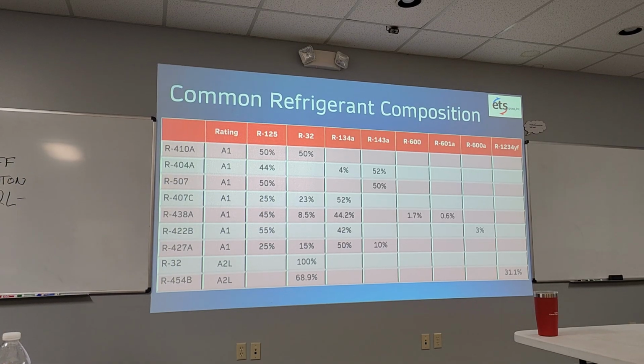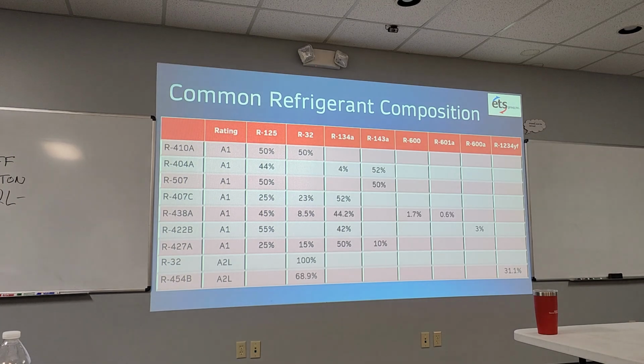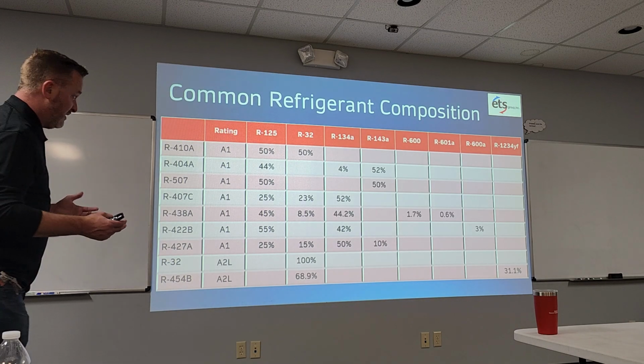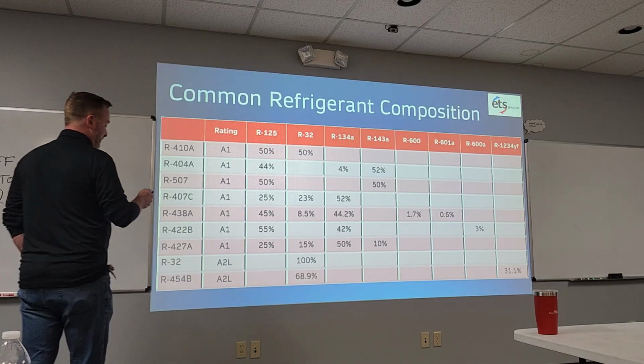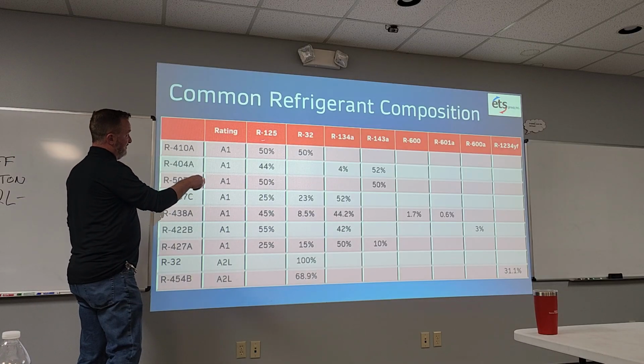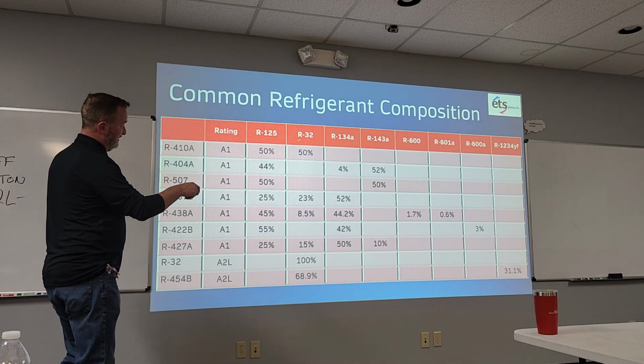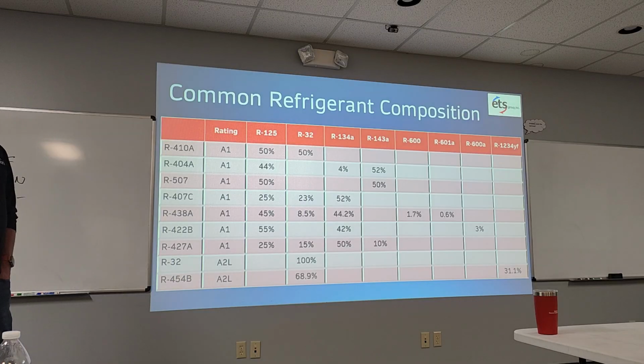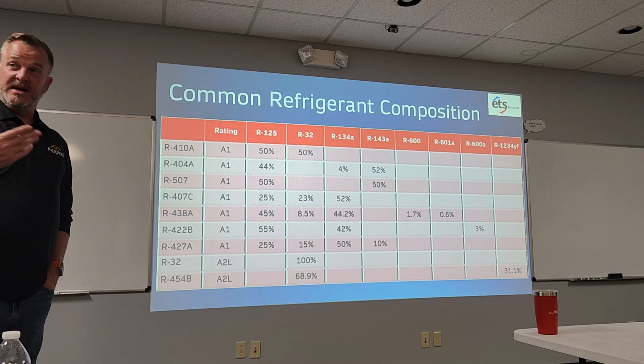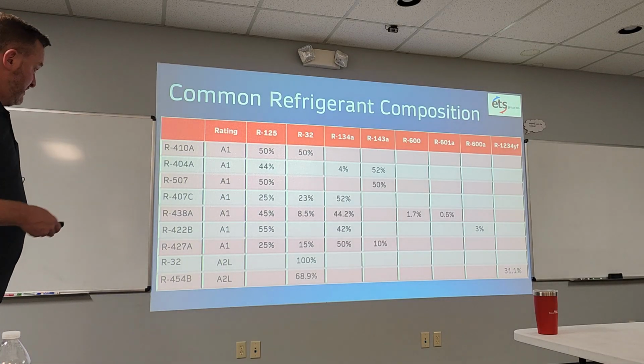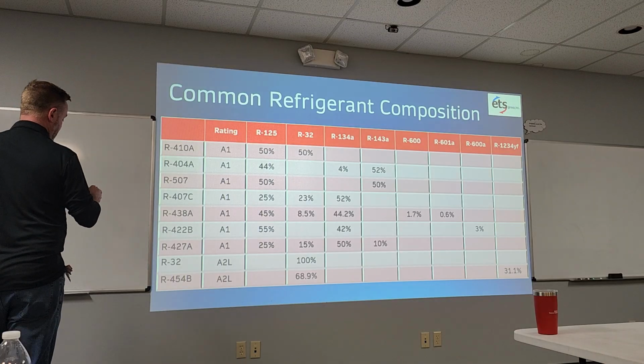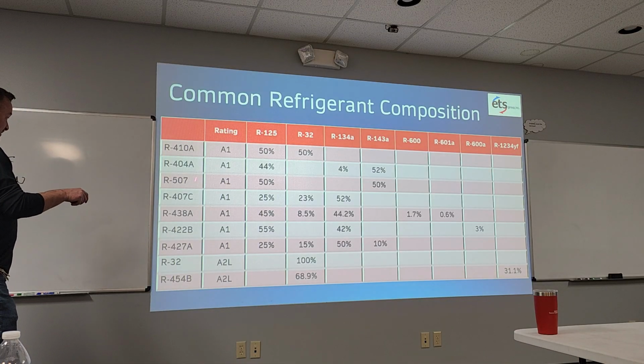R32 is one of the A2Ls that we're gonna be working with, right? Pretty much your main two, there's some other ones out there, but your main two are gonna be 454B and 32, which we'll talk about. So that's what I mean when I say this is considered a fire suppressant. R32 is a mildly flammable refrigerant, that's why it carried an A1 moniker with it, because you had the 125 mixed in with it.